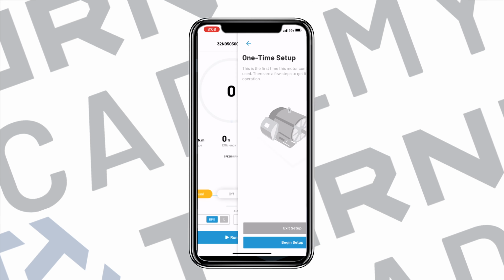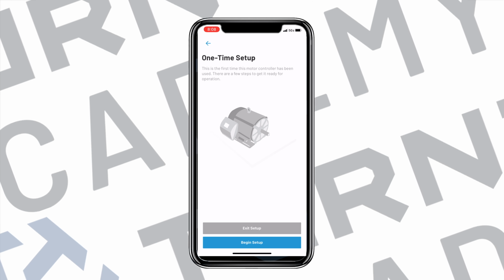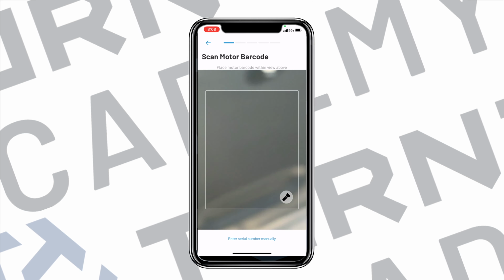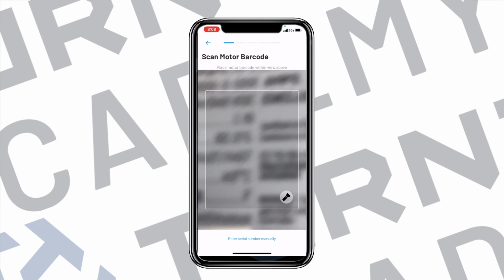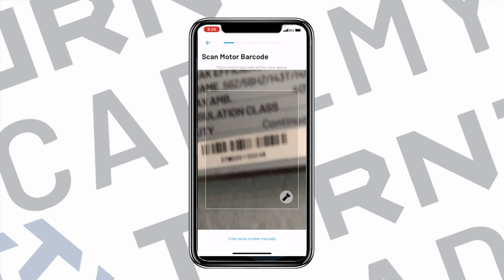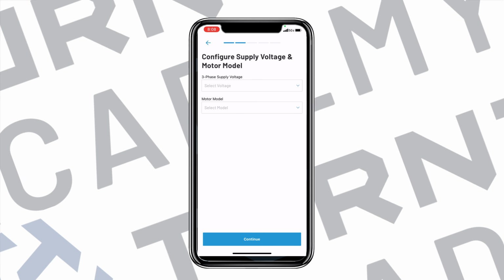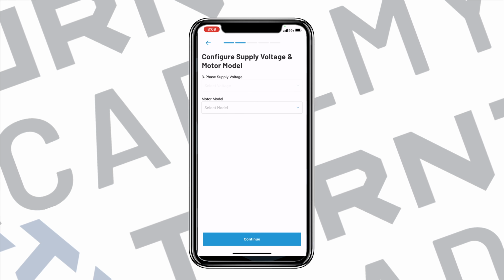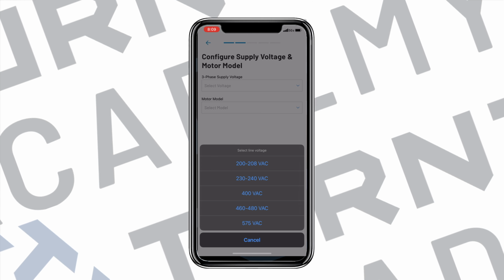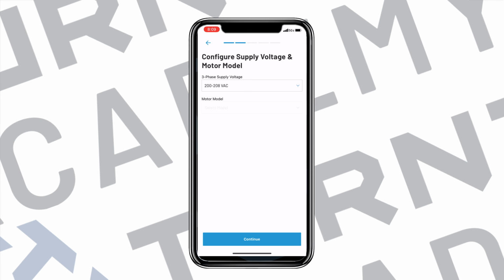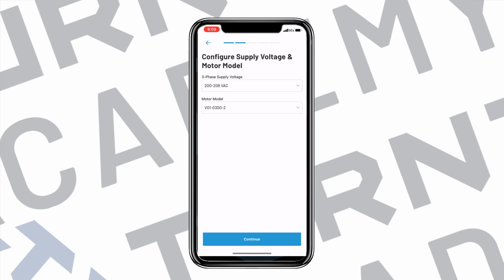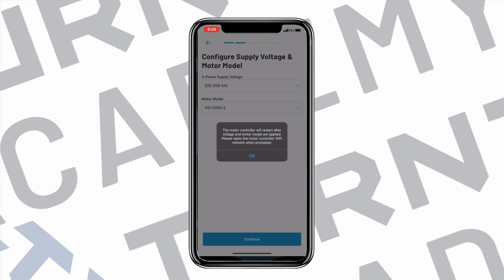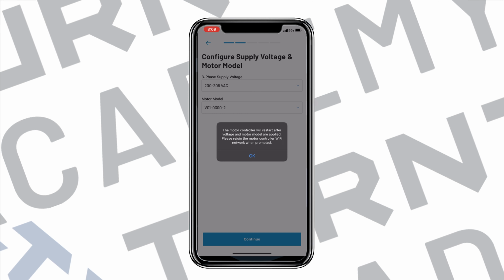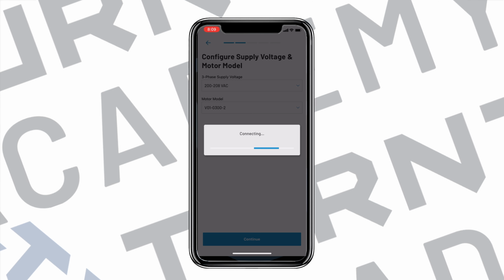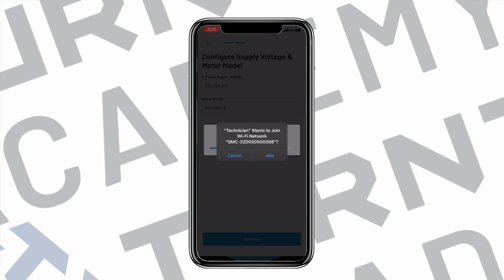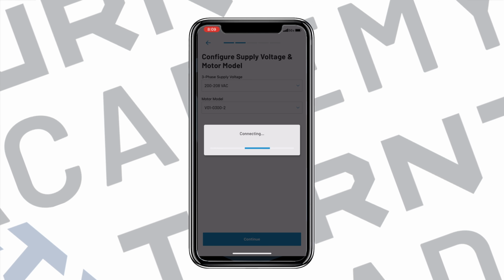After connecting, the setup screen appears. Touch Begin Setup and scan the Turntide motor barcode. Following a successful scan, the supply voltage and motor model screen appears. Touch the first drop-down and select the correct voltage applied to the motor controller. Next, touch the Motor Model drop-down menu and select the correct Turntide motor model. Acknowledge the notice that the motor controller will restart. When reconnection is complete, rejoin the controller network.